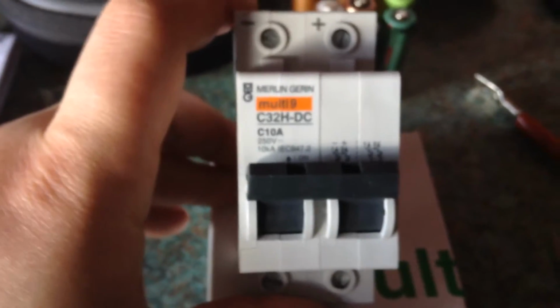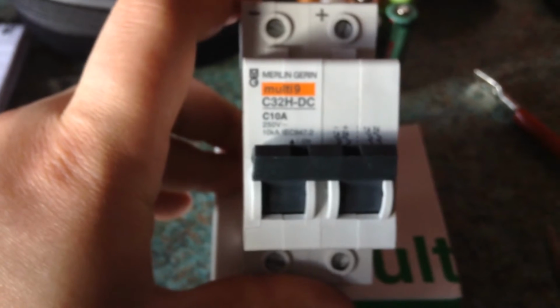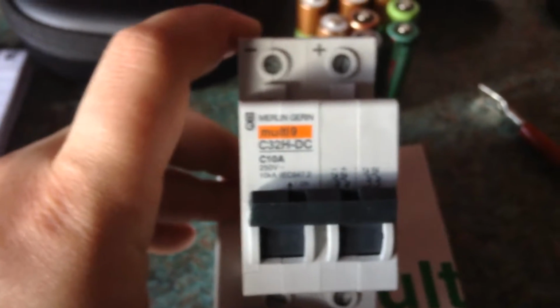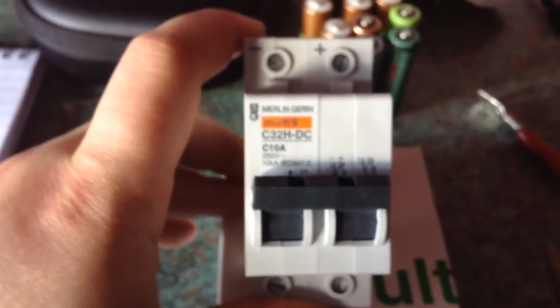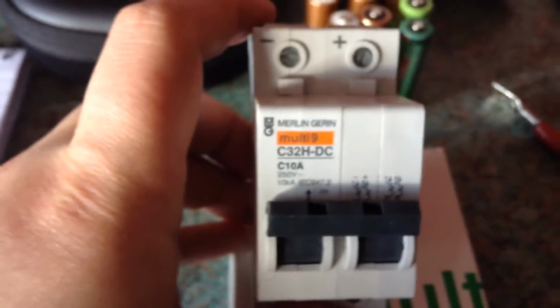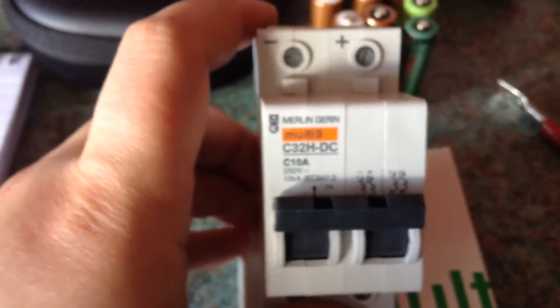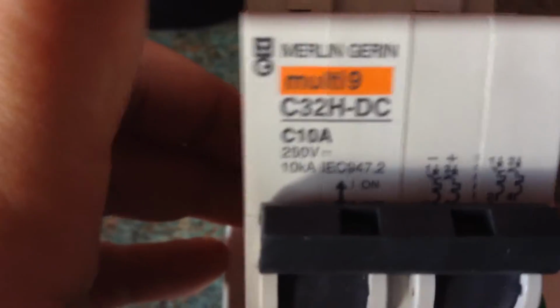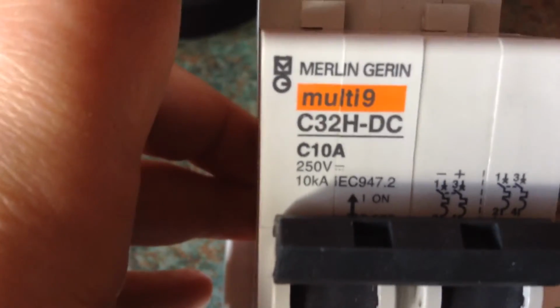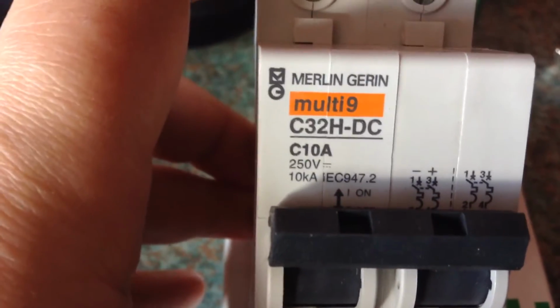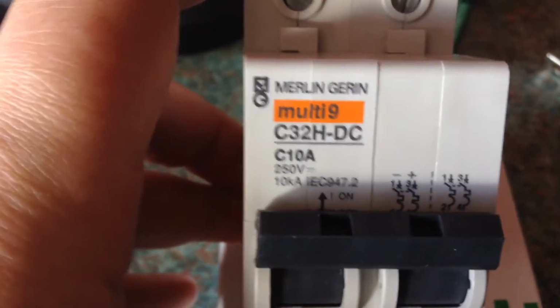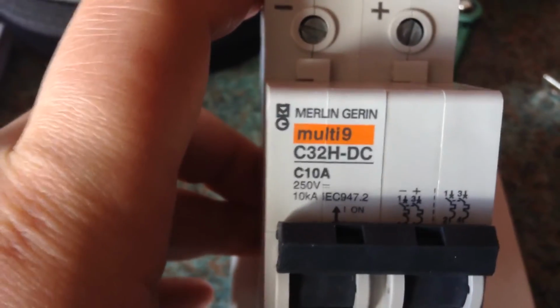Using an AC breaker can lead to a fire hazard, so don't use them. DC breakers are a bit more expensive - this 10 amp breaker cost £10.50, so not overly expensive, but better to buy the right item for the job. This is a Merlin-Gerin Multi-9 C32H DC 10 amp circuit breaker, rated for up to 250 volts DC and can interrupt a current of up to 10,000 amps, so that is fine.